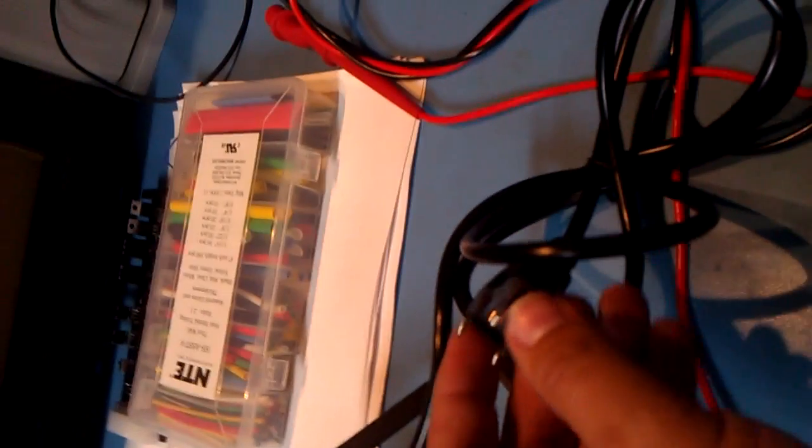The first thing I did upon receiving the unit was check between the ground plug and a metal screw here into this chassis. This is powder-coated metal, and I did get a nice 0.2 ohms as expected, and I was feeling pretty happy and confident about that.